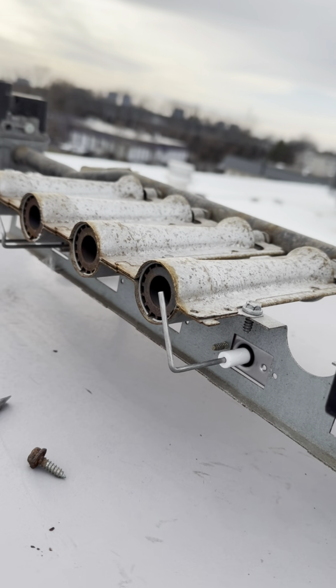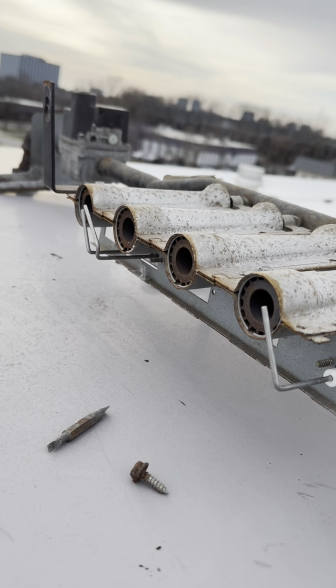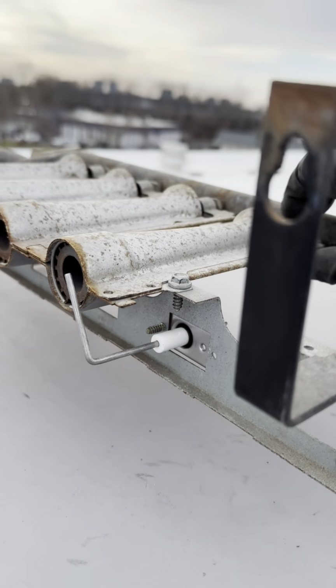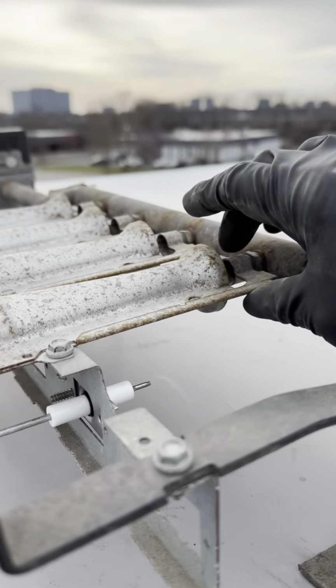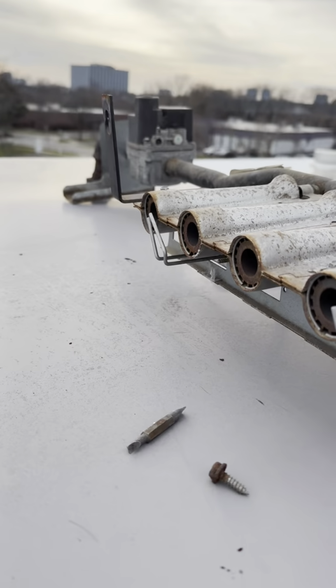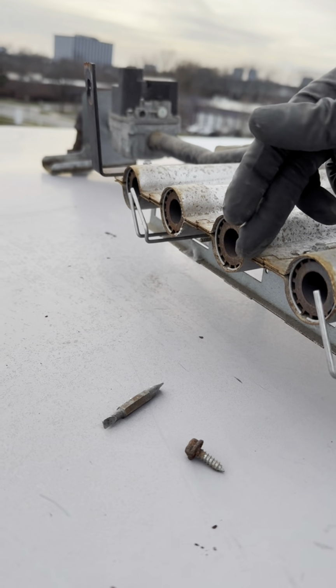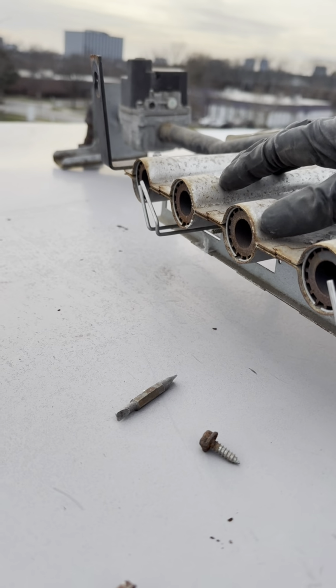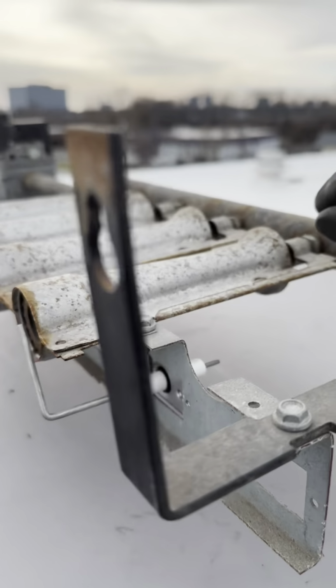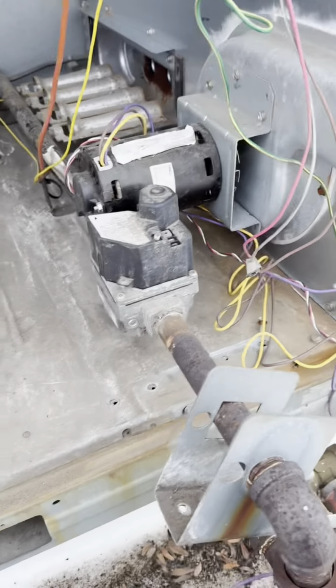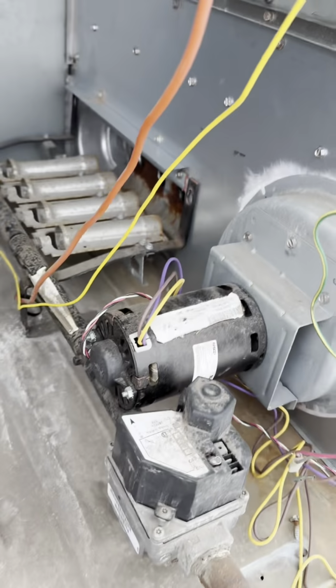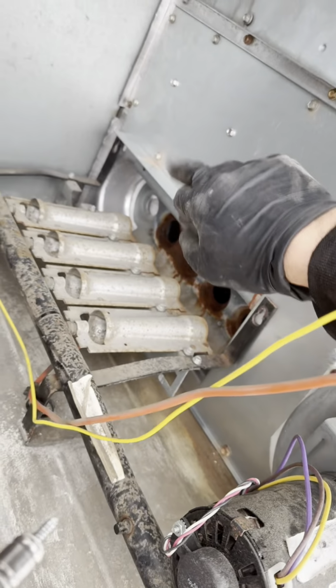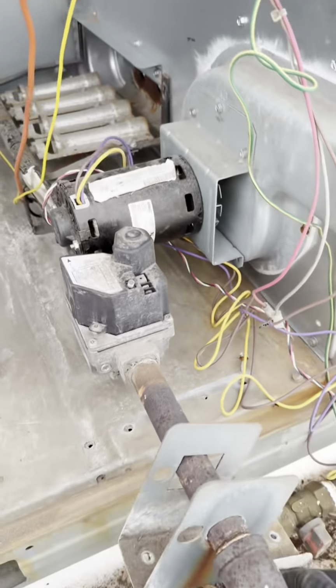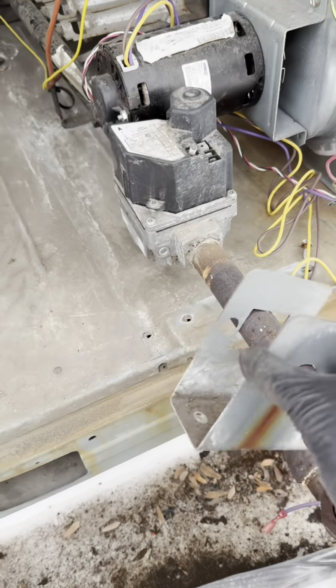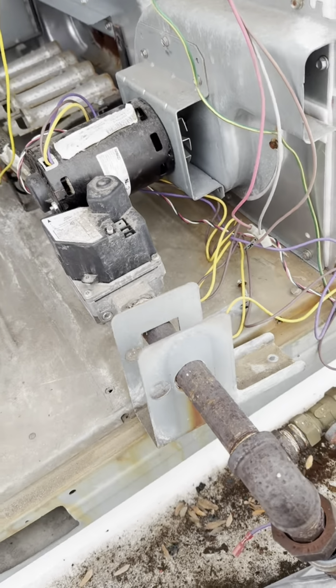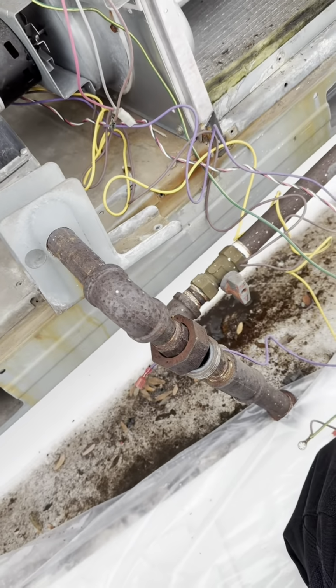I'm going to go ahead and clean the burners since I have it out here. Poke the orifices, make sure there's no creature that crawled in there, and make sure everything is aligning so that we don't have an issue. We are now putting the burner back in. I'm going to get it screwed in to secure it at 2 points, and then put the gas valve bracket in and tie in the gas.